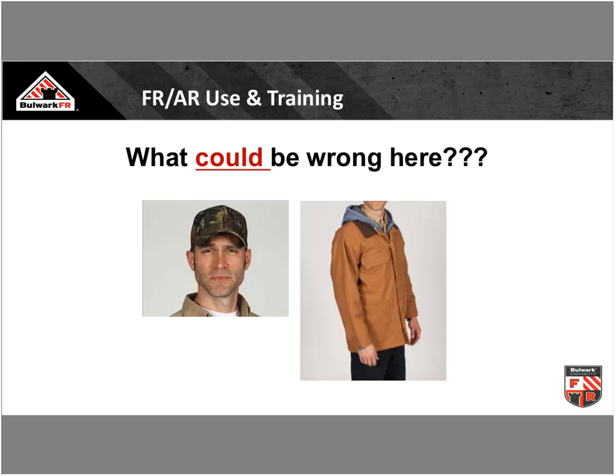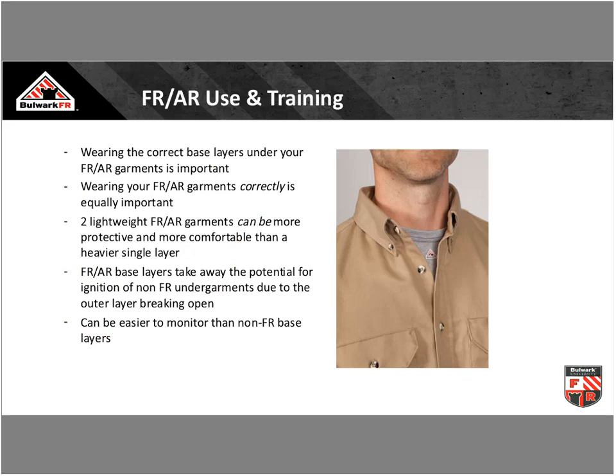Take a look at this very expensive flame-resistant arc-rated brown duck coat, and now I see this hoodie sitting out over the top of it. Well, if you remember our standards and regulations, the outermost layer has to be flame-resistant arc-rated, so that hood just became the outermost layer. Is that hood flame-resistant arc-rated? Or did I just put my 65-35 hoodie on underneath, or my 100% cotton hoodie underneath, or what is that? I don't know, but if it's not FR, that's a big hunk of fuel you've got sitting on the back of your neck. When you turn away from that arc flash and expose it to all that energy, it could ignite, and then you've just jeopardized that whole program.